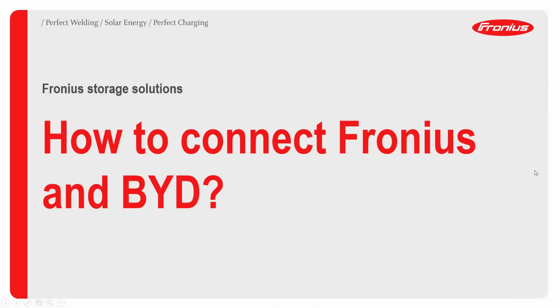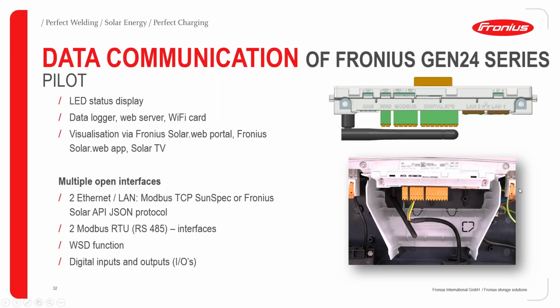So much to the news in Solar.web, and a special topic I've integrated for today because it's commonly asked is how you connect a Fronius inverter to BYD and how this is done correctly. Principally, we have had this pilot, this communication card already, sitting in the middle of the Fronius inverter. Every Fronius Gen24 Plus device is standardized equipped with this pilot, which is our data communication card where all these multiple open interfaces are integrated, and the BYD battery is then connected via this Modbus plug I will show you here.